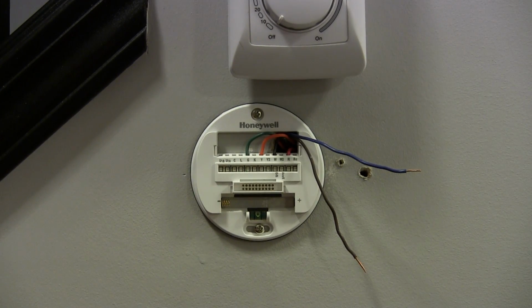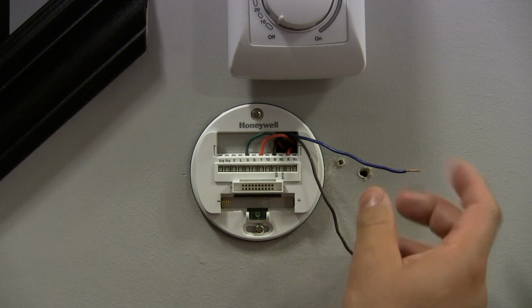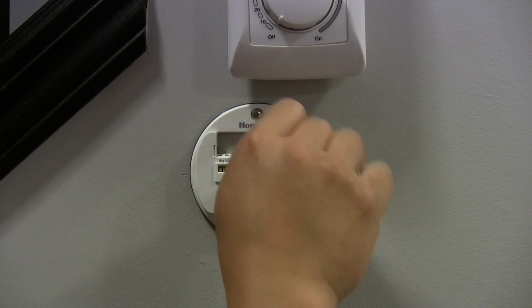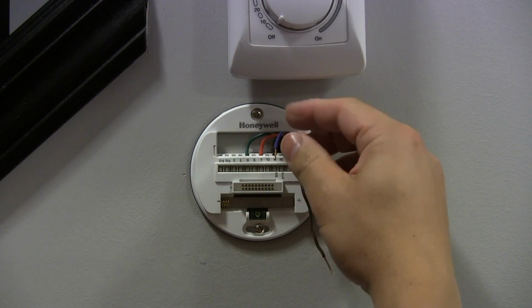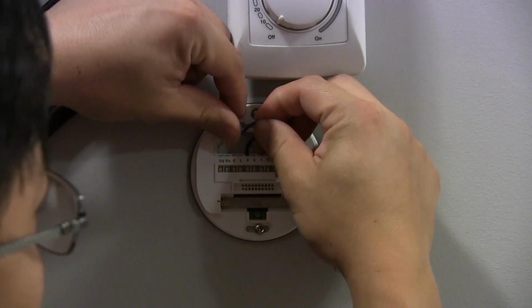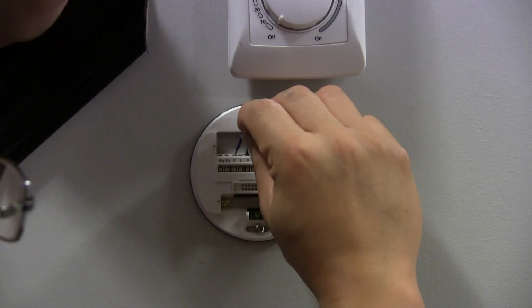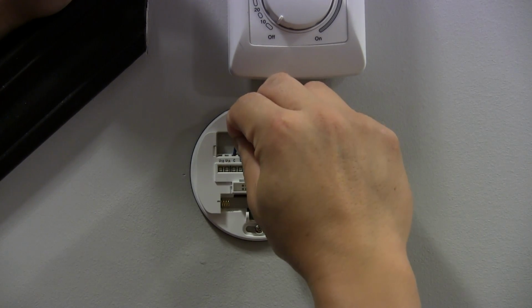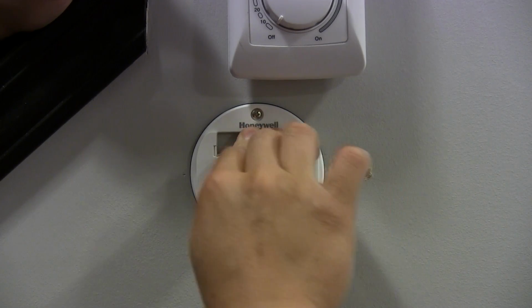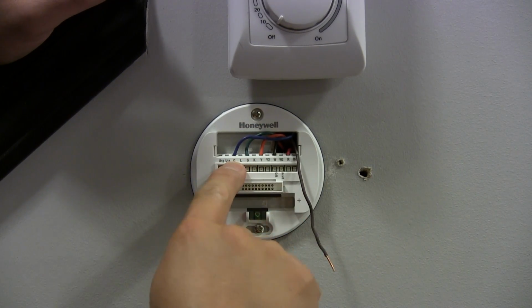After doing some research as well as probing around inside the control box of our furnace, it was identified that this blue wire that was controlling the humidifier is actually the common wire that goes onto the furnace control board, which supplies 24 volts AC for the humidifier water solenoid. So we can just push this blue terminal into the common connector.